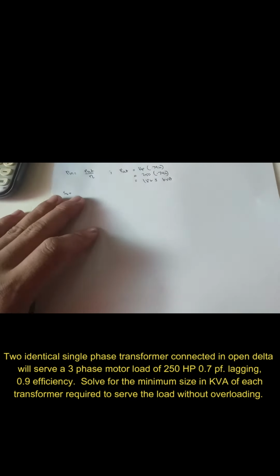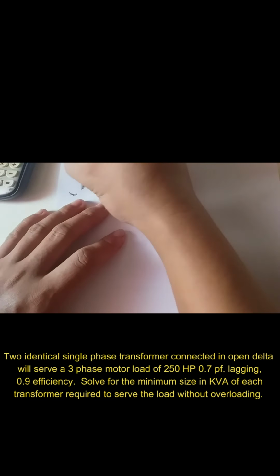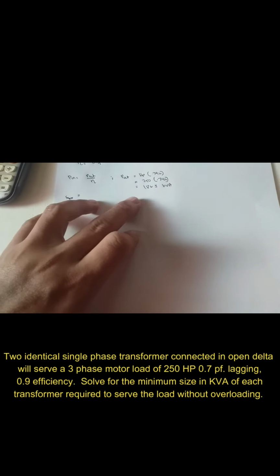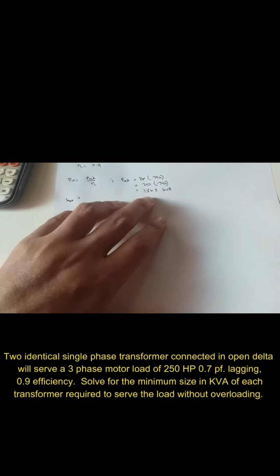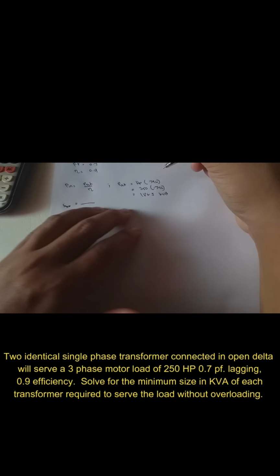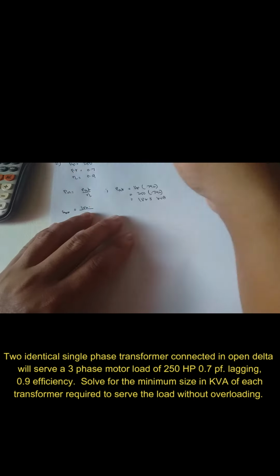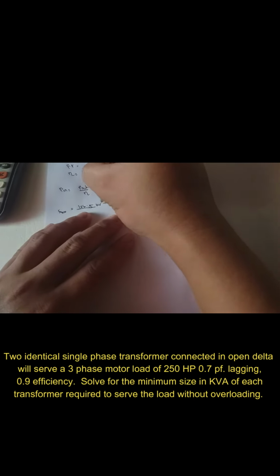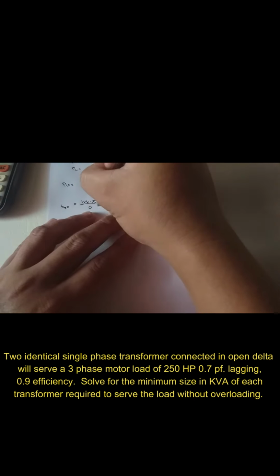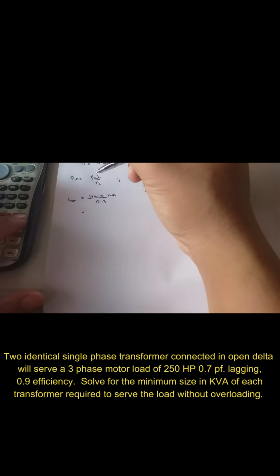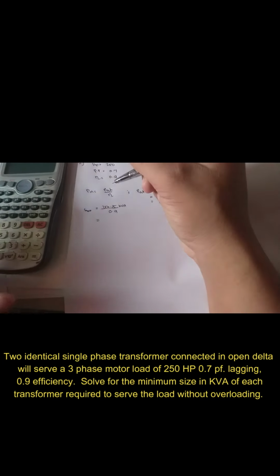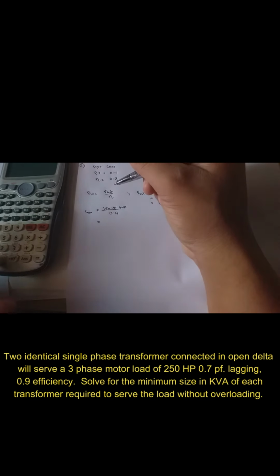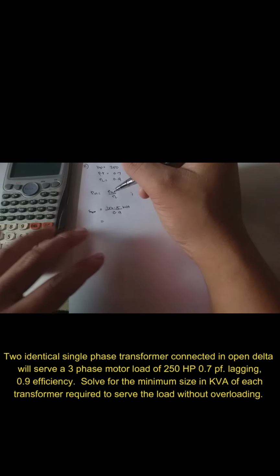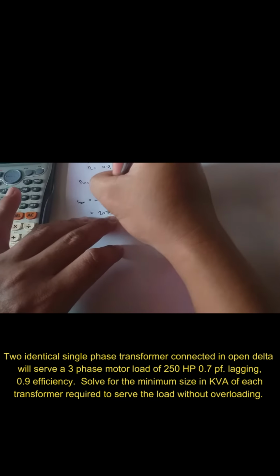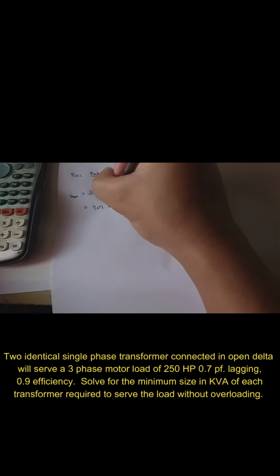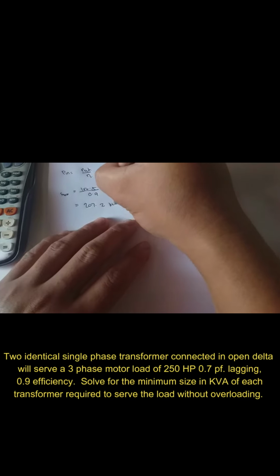So we'll proceed to the total apparent power. Before we compute the total apparent power, we'll compute the input power, because we have computed the output power. The output power, which is 186.5 kW, over the given efficiency of 0.9, is equal to 207.2 kilowatts.